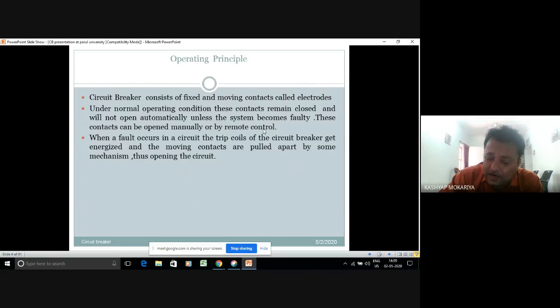I'm using the word remote control now. It means that in the control room, the operator is sitting. From his panel, he can shut off your breaker, even without visiting the substation or site. The prime requirement of the maintenance engineer is that he or she should be able to read the readings and trace the control circuit. That is also one part of preventive maintenance, that they have to verify that this circuit is working okay, and in future it will keep working well.